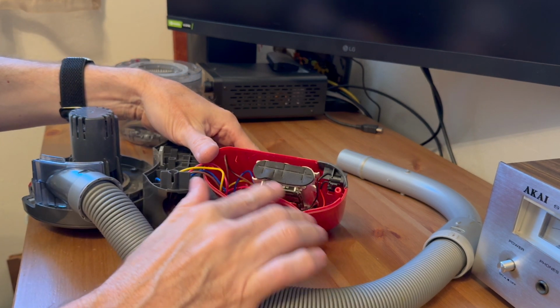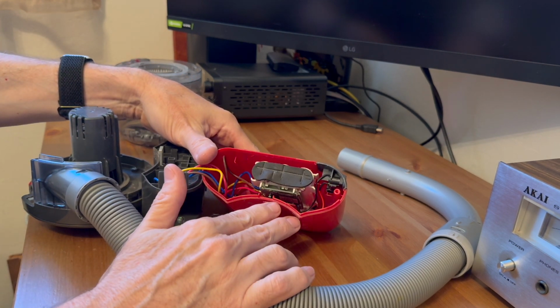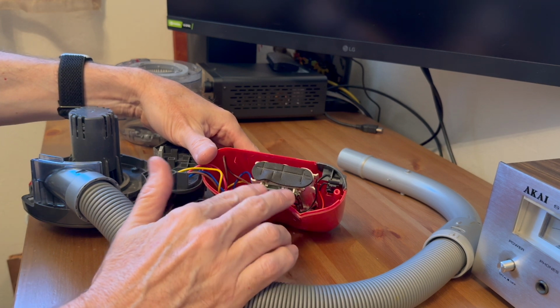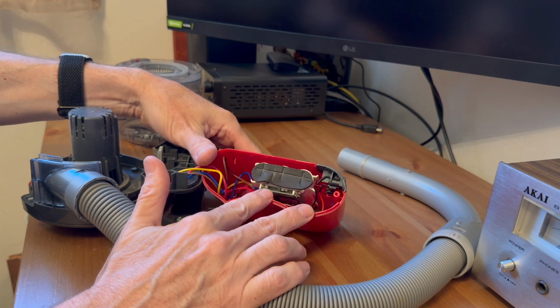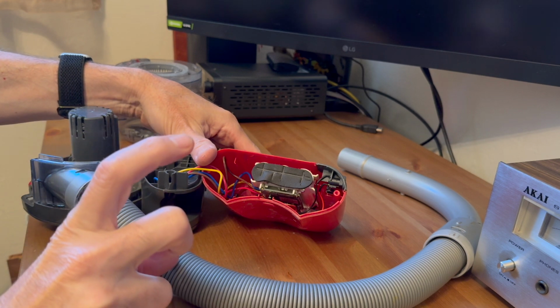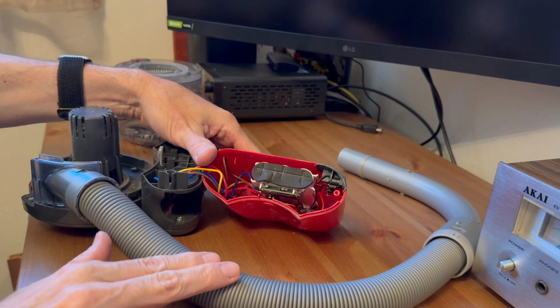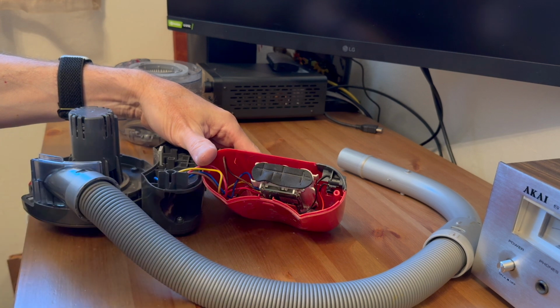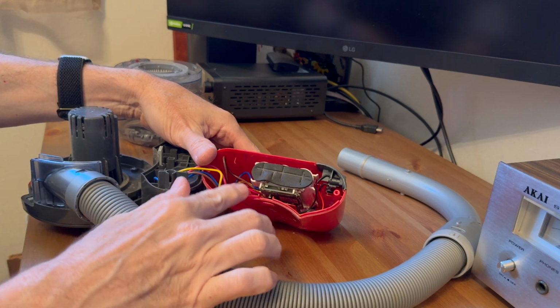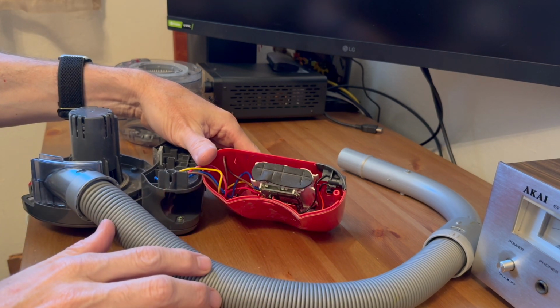So what happens is these things have what's called a battery management system. What that does is make sure each battery stays within a certain range of voltage, meaning they don't discharge below a certain voltage and they're not charged above a certain voltage. Each battery is checked individually.